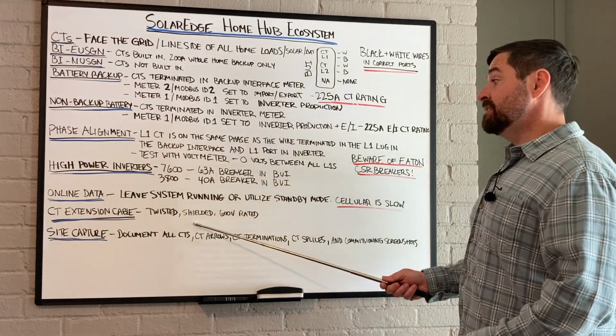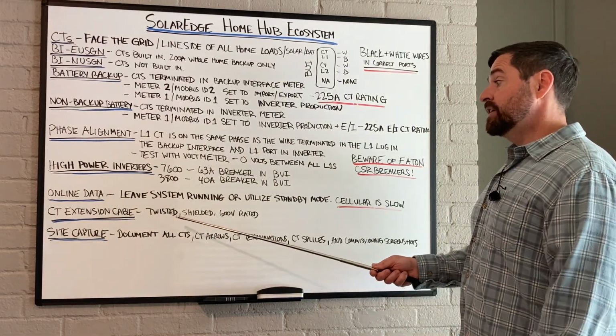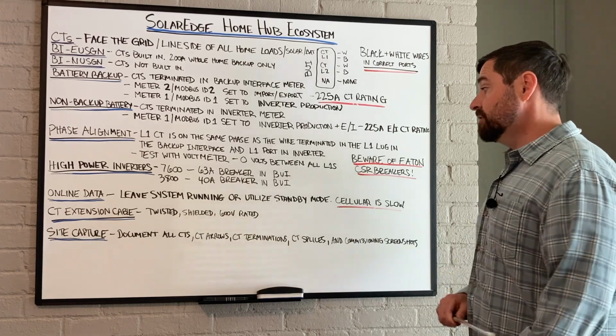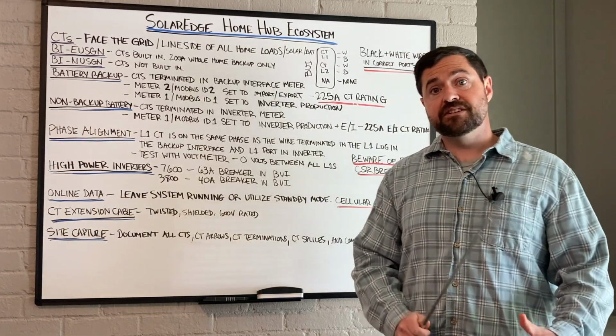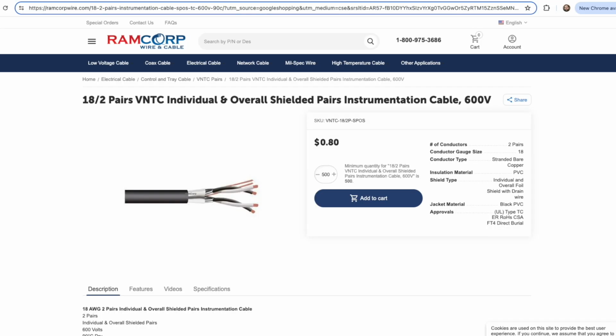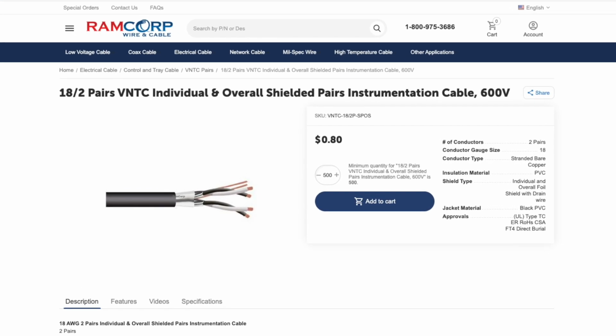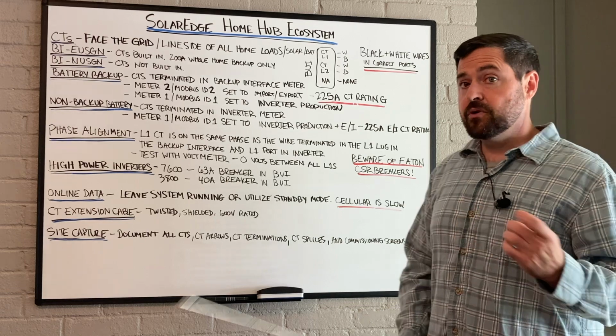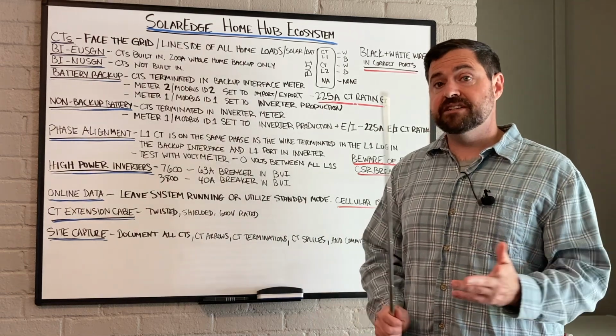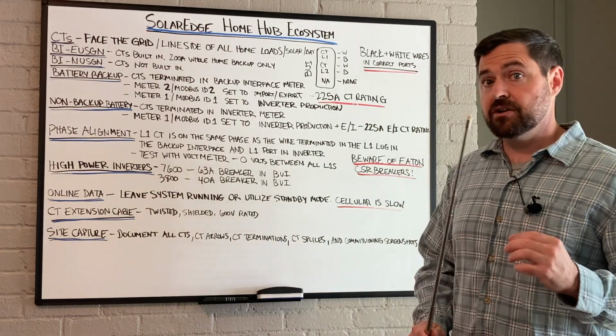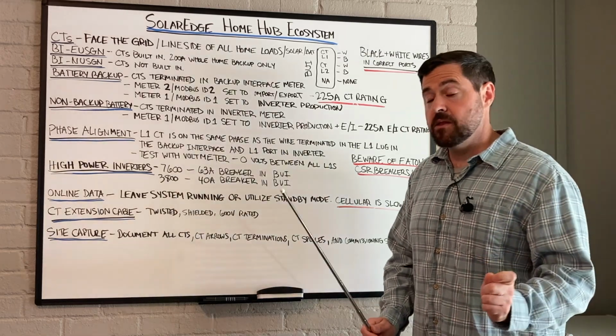If you ever extend the CTs, you're going to want to use twisted, shielded, 600 volt rated CT extension wire. Every crew should have a roll of this on their vans for extending CTs. You never want to rig up CT extension wires from anything else. It's just going to cause you more problems and headache in the long run.